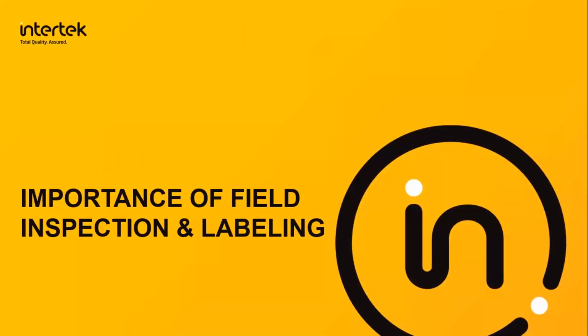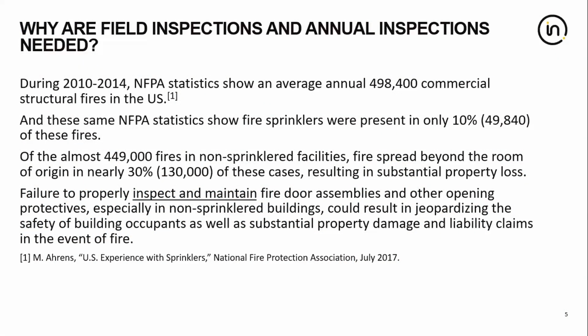So let's start out with some background information, the importance of field inspection and labeling. Why are field inspections and annual inspections needed? If we look at some of the statistics between 2010 and 2014, NFPA statistics show an average annual 498,400 commercial structural fires in the United States. Within these statistics, fire sprinklers were present in only about 10% of those fires. So you have almost 450,000 fires during that period of time in non-sprinkler facilities. And in those cases, nearly 30% or 130,000 had the fire spread beyond the room of origin, resulting in substantial property loss and potentially the loss of life.